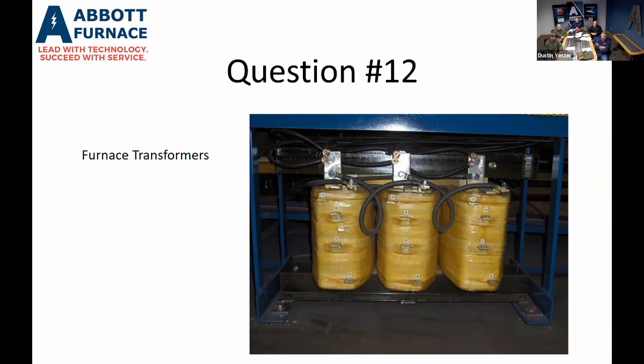That's one of the telltale signs of glow bars being mismatched or imbalanced. Then if you determine that your load is balanced and you're just not pulling enough amperage, then you can go up a tap, and then you just take each one of them legs, those lugs right there, and you move it down to the next tap. You want to make sure that you do all 3 banks the same, because this is a 3-phase system. They're not separate phases.